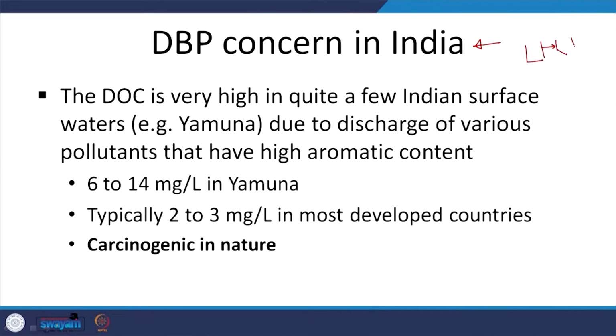So, that is why, whenever wastewater treatment plants in India use chlorine, they do it for two reasons. Their activated sludge process or the biological treatment does not work very well due to poor maintenance or poor operation, sludge retention times being very low, and so on. So, here they use chlorine for two purposes, not just for disinfection. Chlorine is also an oxidizing agent, so you can oxidize the organics left, and it will be as if BOD is less. But by adding this amount of chlorine, you are forming a lot of disinfection byproducts which you are releasing into the water body, greatly affecting and killing aquatic life.